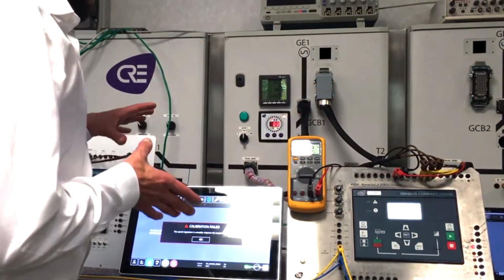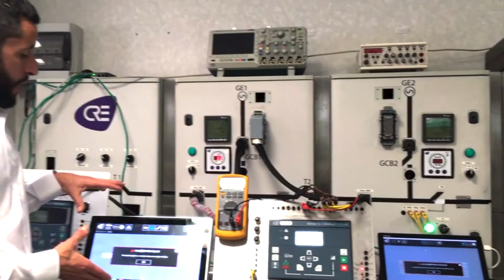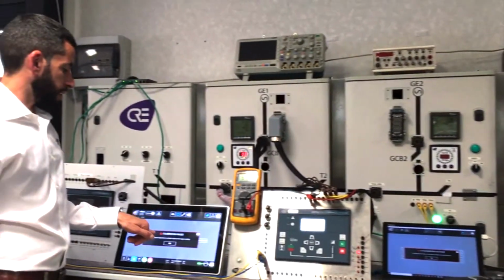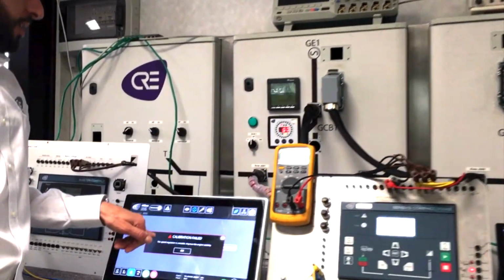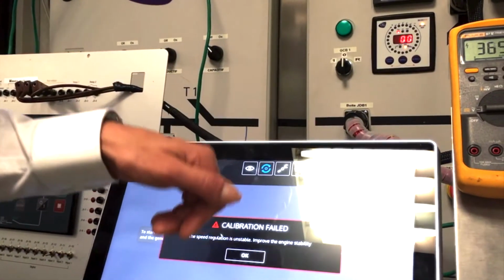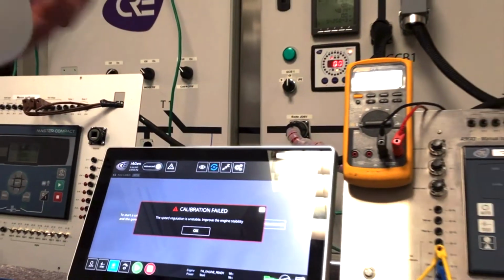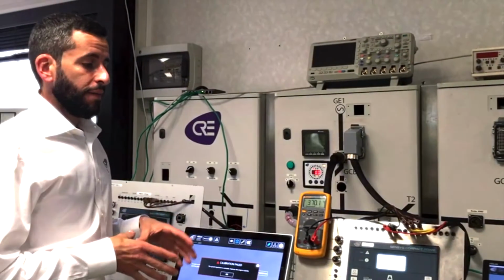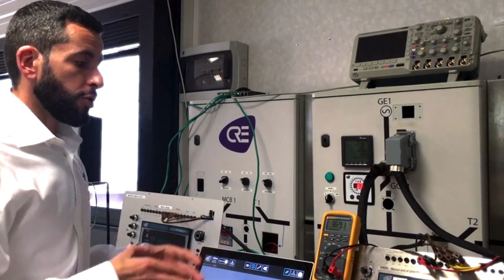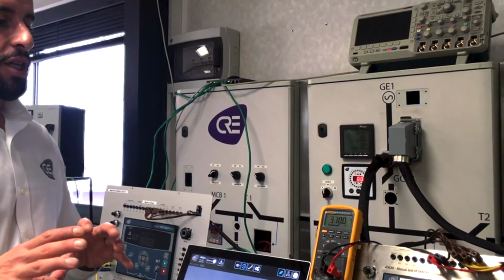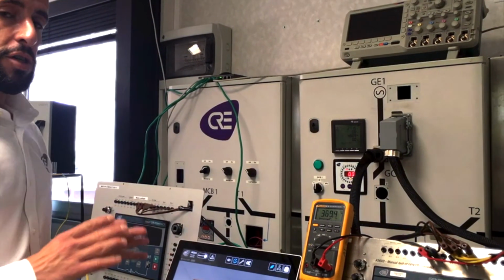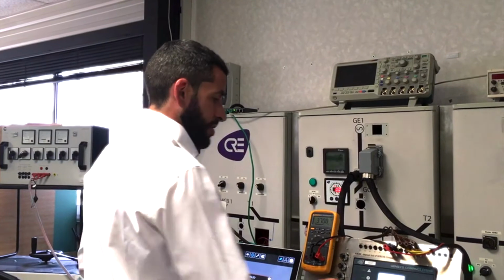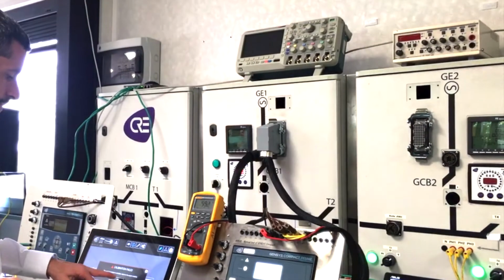So, at the end of our first try, we have seen that the frequency was oscillating. I have a calibration fail here. You can look at the message here. It is saying the speed regulation is unstable. Improve engine stability. So I have created this instability with the settings. So EasyCalib has detected that the most important part of the engine setup, voltage setup, is wrong. It is telling us first check the genset, check the stability, then after restart EasyCalib. So I will stop the genset and correct the wiring.